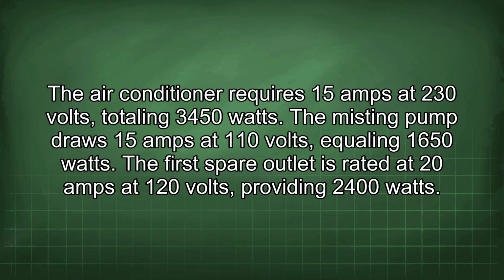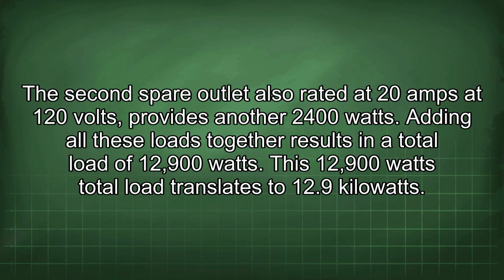The misting pump draws 15 amps at 110 volts, equaling 1650 watts. The first spare outlet is rated at 20 amps at 120 volts, providing 2400 watts. The second spare outlet, also rated at 20 amps at 120 volts, provides another 2400 watts. Adding all these loads together results in a total load of 12,900 watts. This 12,900 watts total load translates to 12.9 kilowatts.